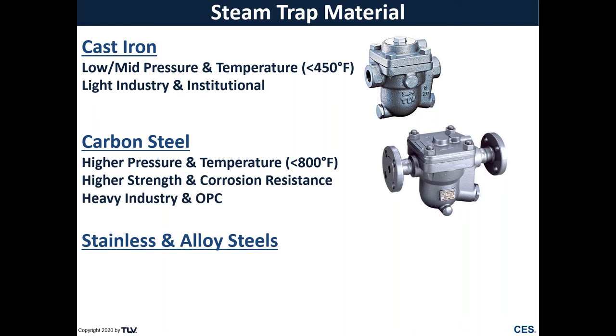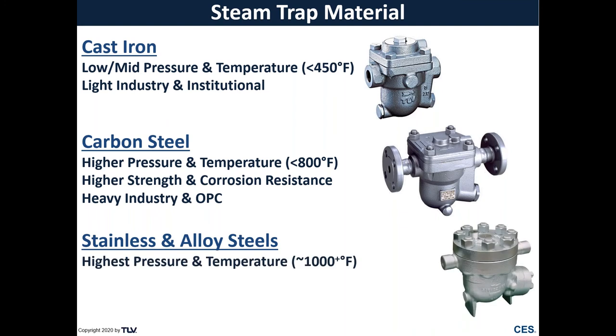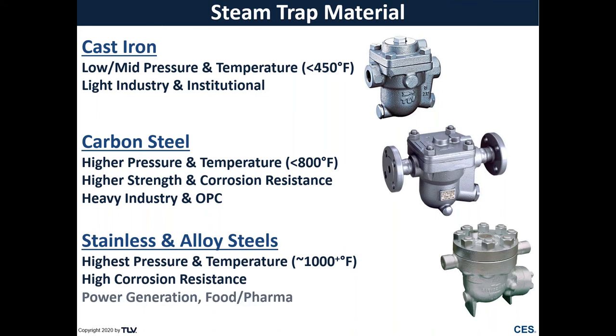And then the third type of materials we see are stainless steel and alloy steels. These generally have the highest pressure and temperature capabilities, sometimes up to 1,000 degrees Fahrenheit or more, and very high corrosion resistance. And we see this very often in the power generation industry because it is suitable for very high pressures and temperatures. Then we also see stainless in a lot of food and pharmaceutical applications because of its high corrosion resistance.